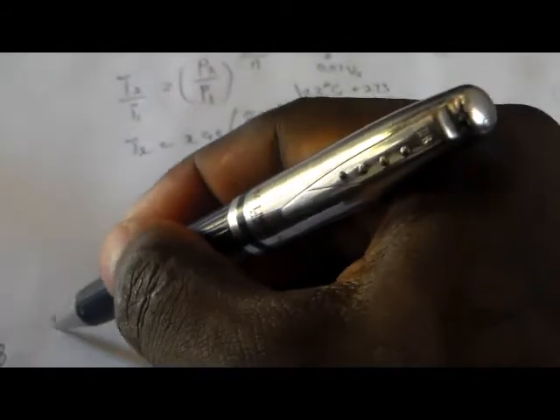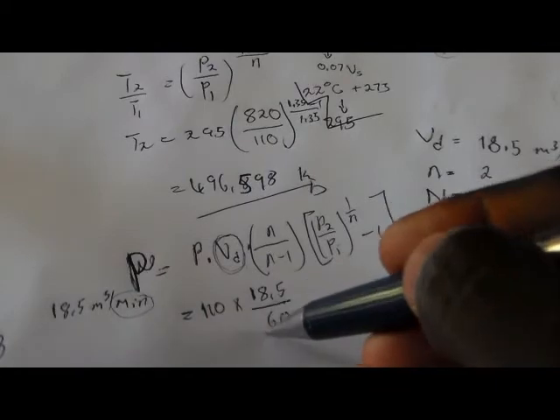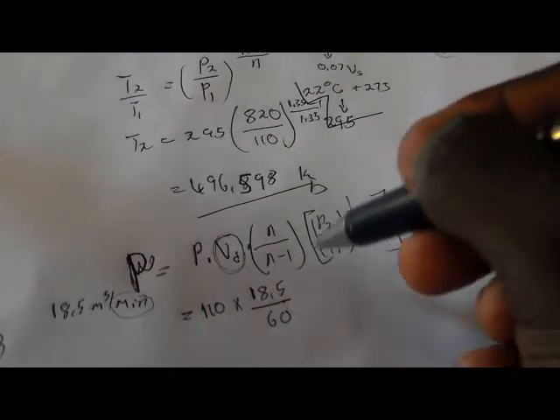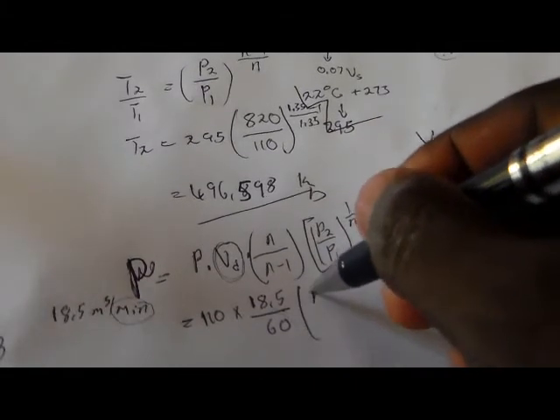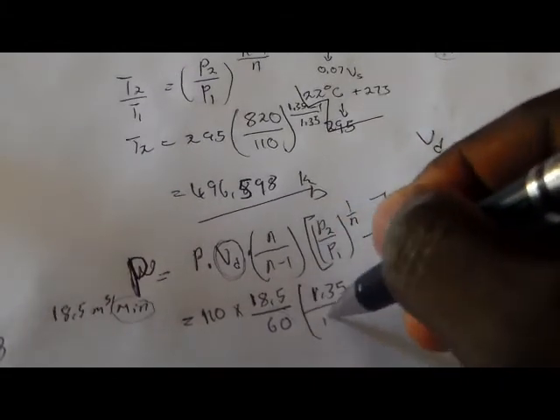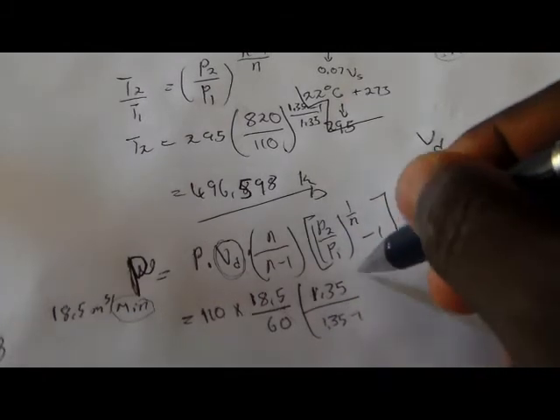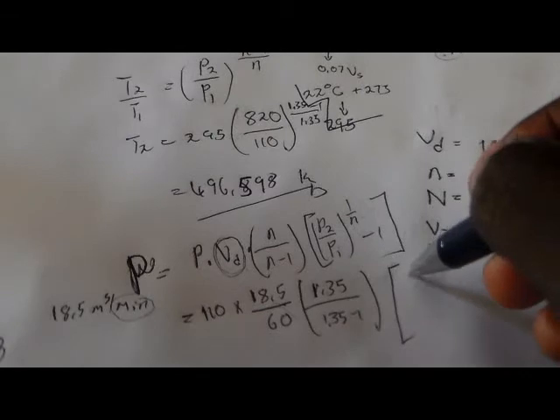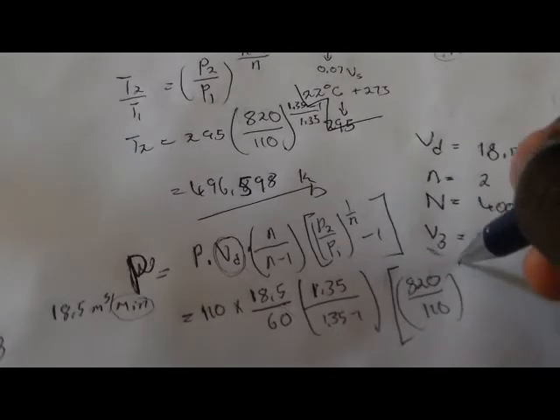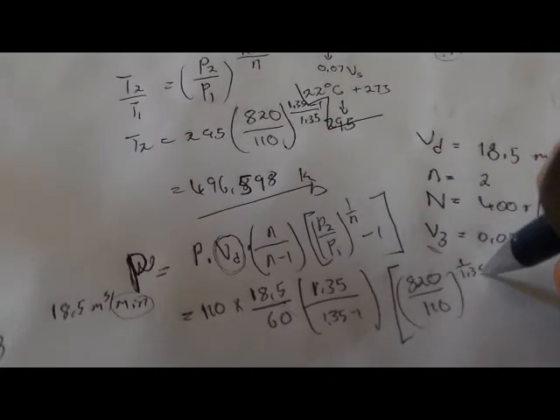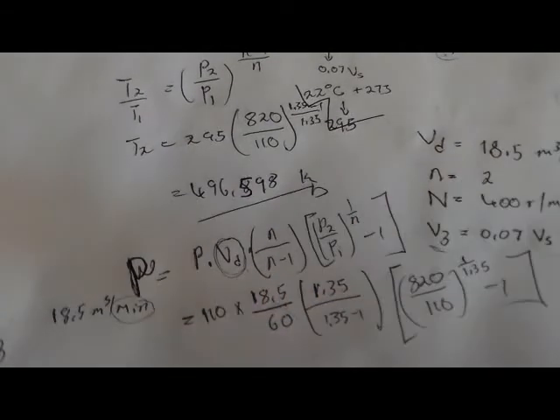The volume delivered is 18.5 cubic meters per minute. When we're calculating the power, we want it per second. Then our index, which is 1.35 divided by 1.35 minus one, to the power — multiplied by pressure number two, 820, divided by 110, to the power 1 divided by 1.35 minus one. So then you find your power.